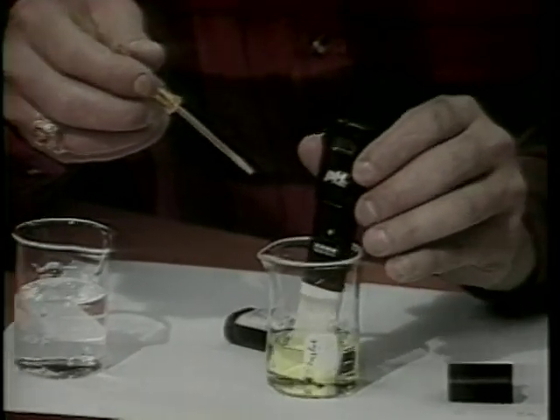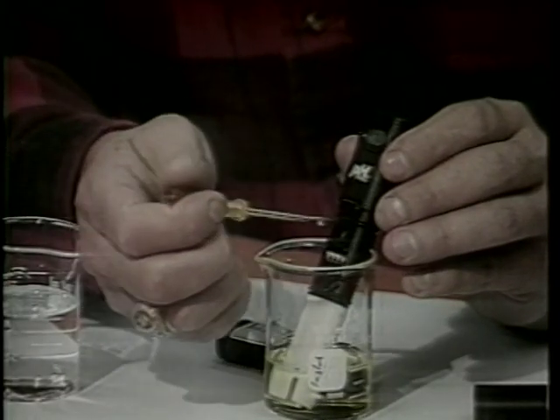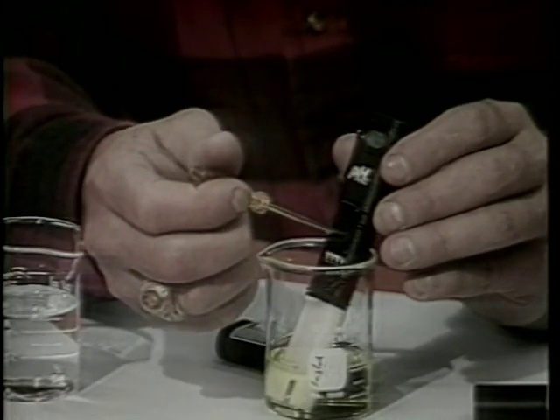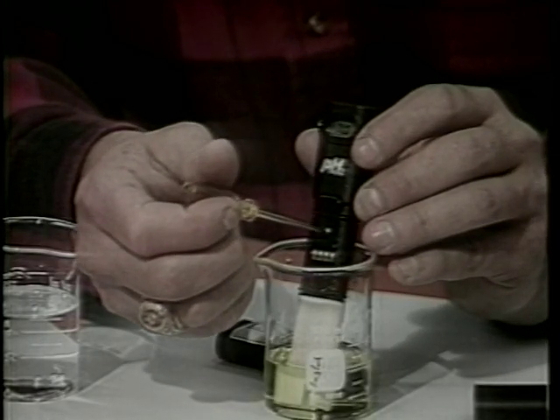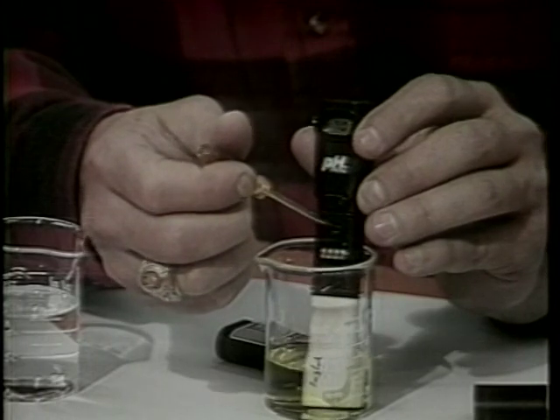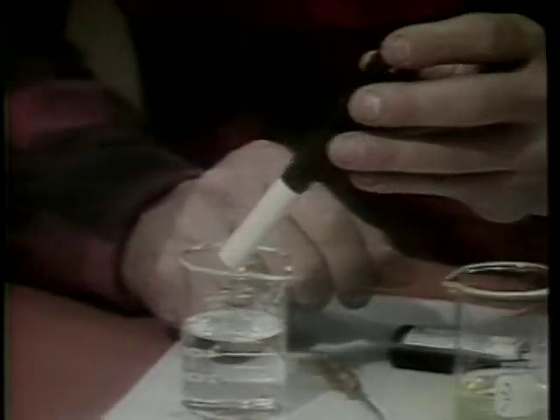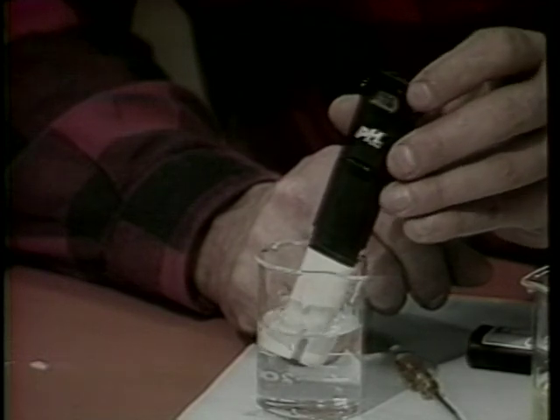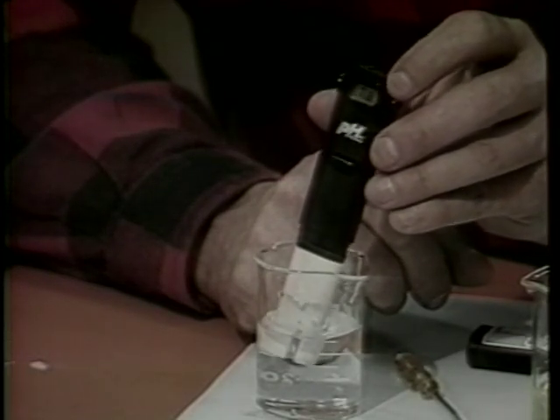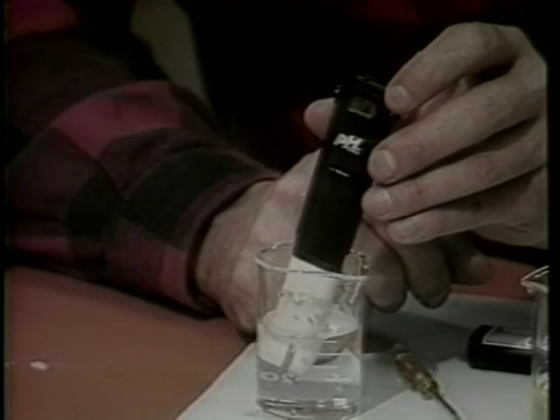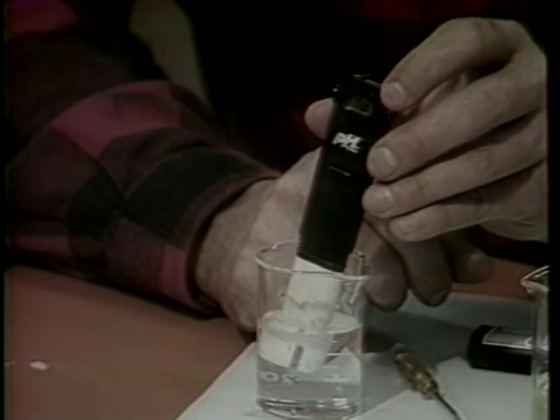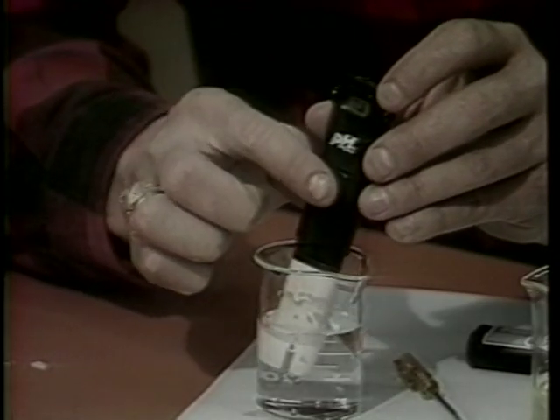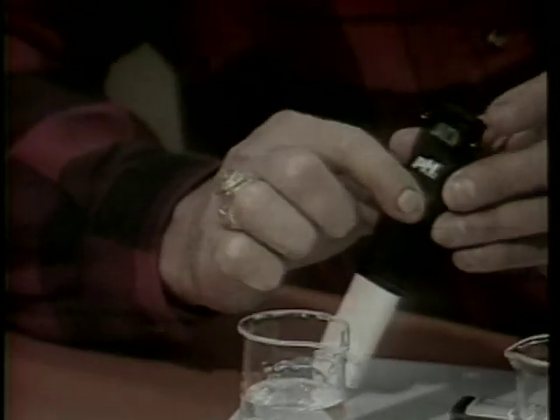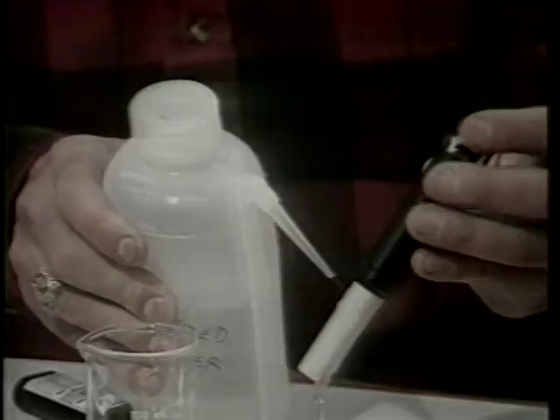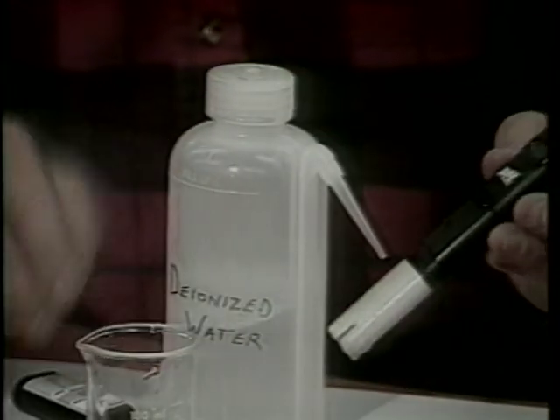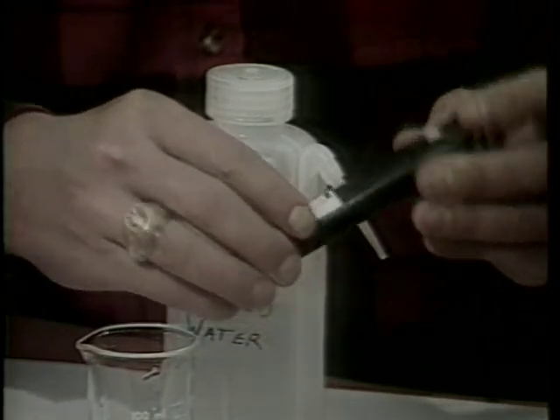Buffers may be purchased from scientific supply companies. To calibrate, adjust the calibration screw until the instrument reads the value of the buffer. Calibration should be done periodically, such as once every few days. To measure the pH, immerse the probe into the water to be sampled. Do not exceed the warning line shown on the meter. Stir back and forth and observe the reading. This particular model has a hold button which will lock the reading on the display after the probe is withdrawn from the sample. After each use, rinse the probe with clean water, preferably distilled if available.